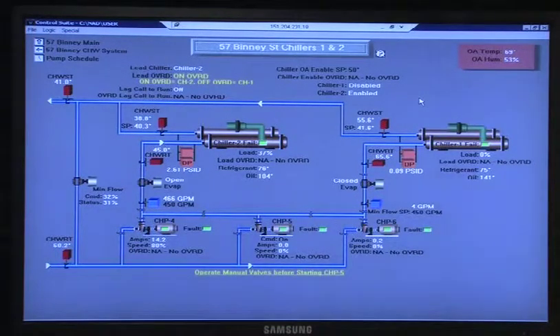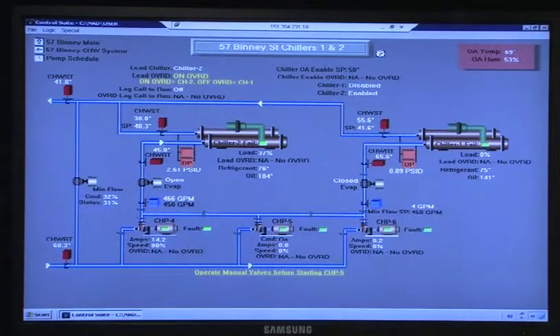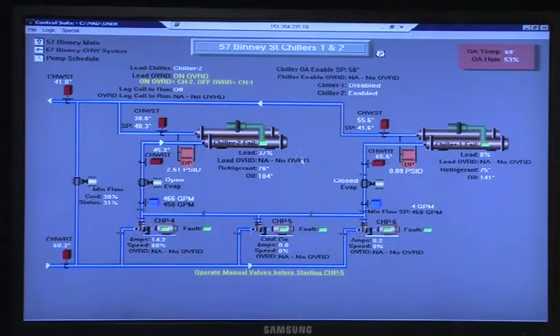That way you can get a lag call to run indication. If somebody either overrides it or it does it itself, at least we'll know there's a condition that exists, because we're not watching this. Jamie can take care of that anytime it turns on. If we know we shouldn't have another machine on, obviously we have a capacity problem, and they have to come in and work on the chiller. I think it's going to be very rare that you end up in that situation.